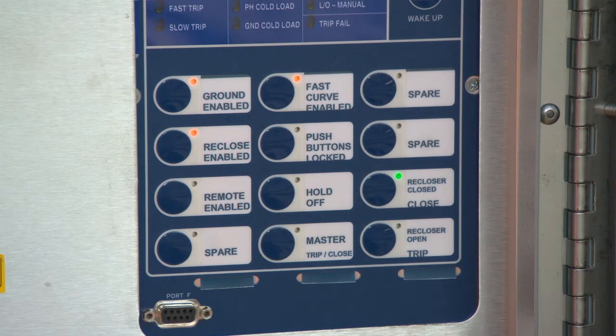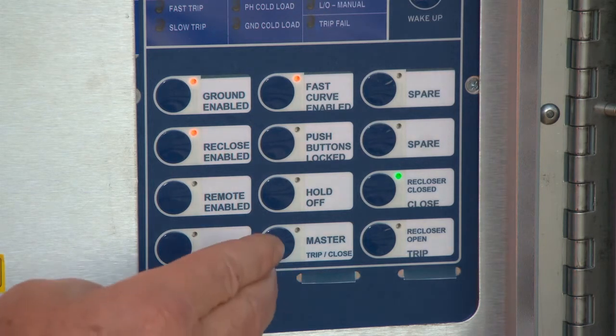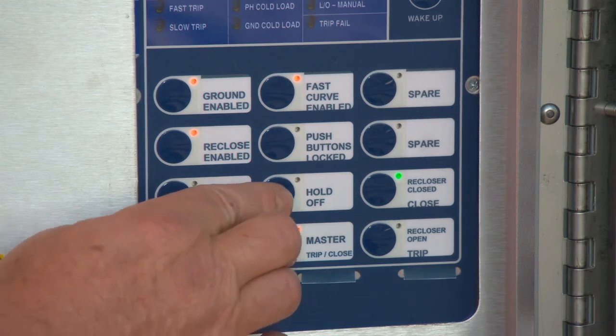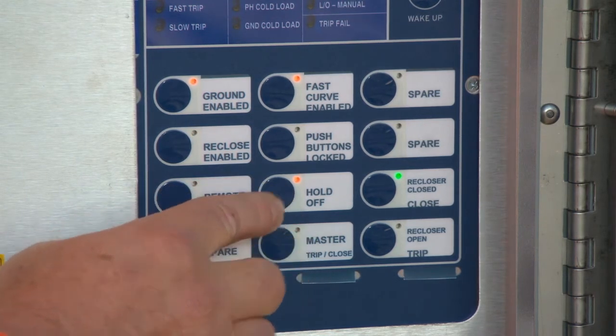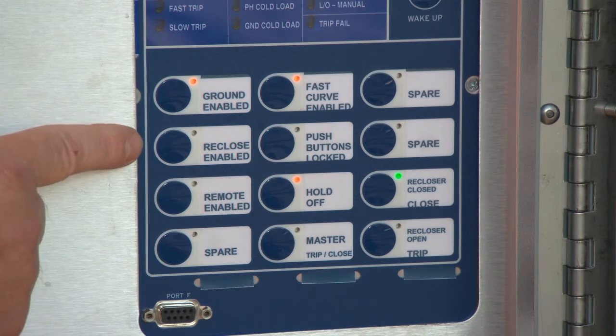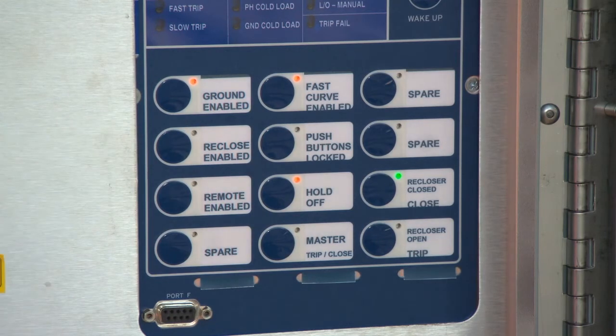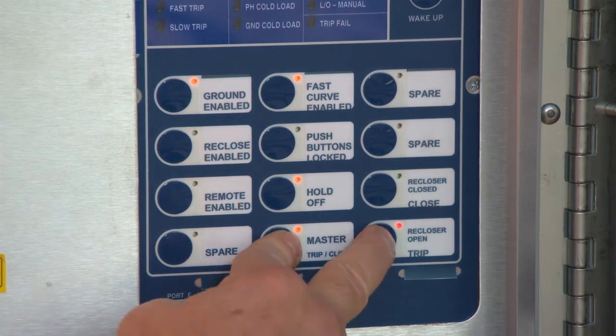Applying the hold-off, or in our terminology, a hotline tag, requires a 2-button operation. Push the master and hold-off buttons together. The Reclose Enable light will also turn off. With the hold-off engaged, the system will respond to a fault or manual trip with a 1-shot lockout. For demonstration purposes, we will manually trip the unit.